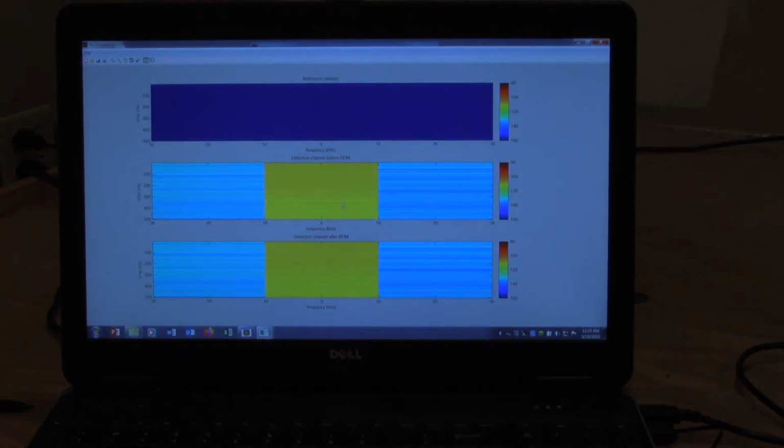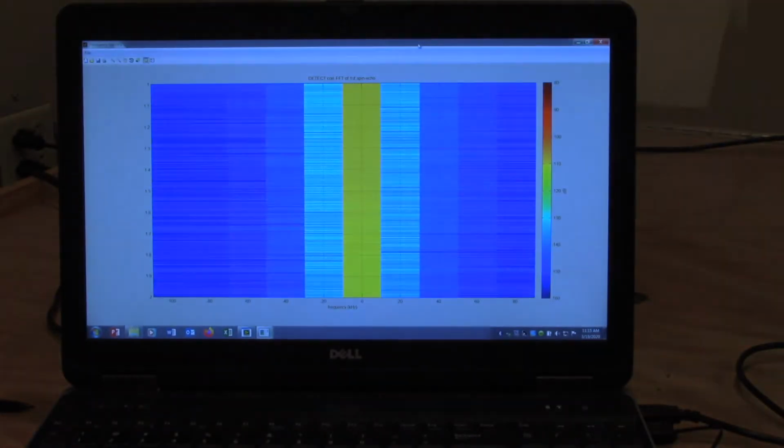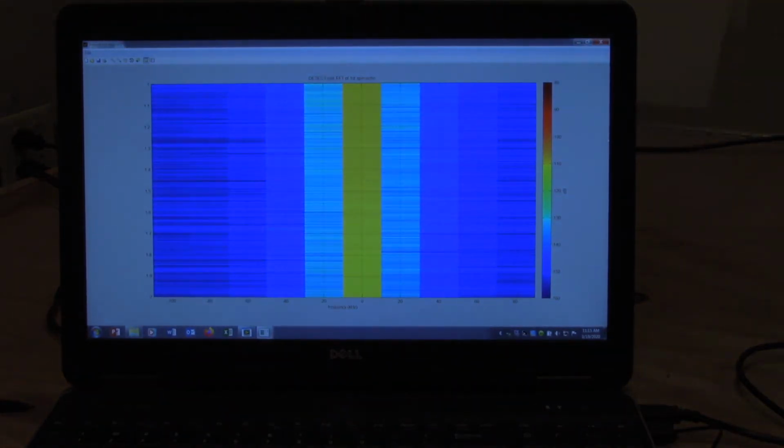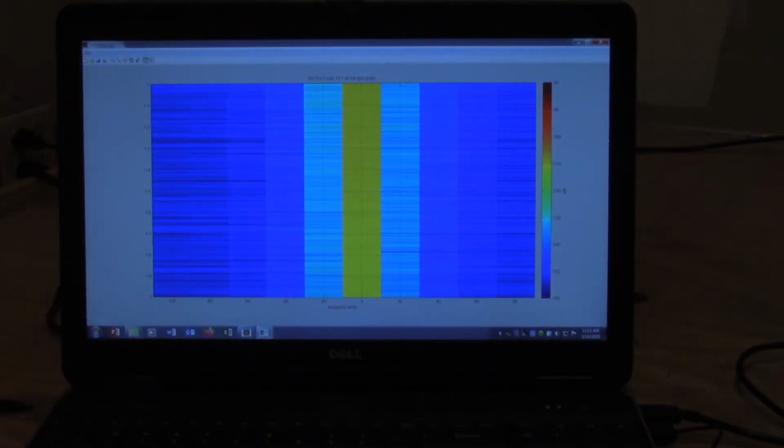Here is another QAQC window, which has to do with the noise level, so there's nothing to see there really. And here's the frequency spectrum, and we want to see all of our peaks aligned around our frequency and constant throughout all of the pulses. So we can see it's centered around zero and it's constant, meaning it's around the Larmor frequency, and so this is good.